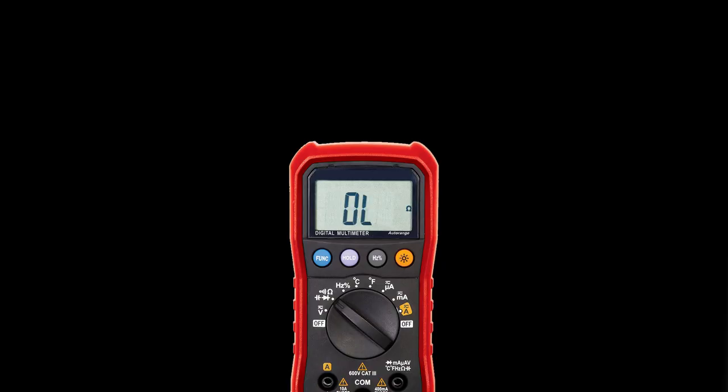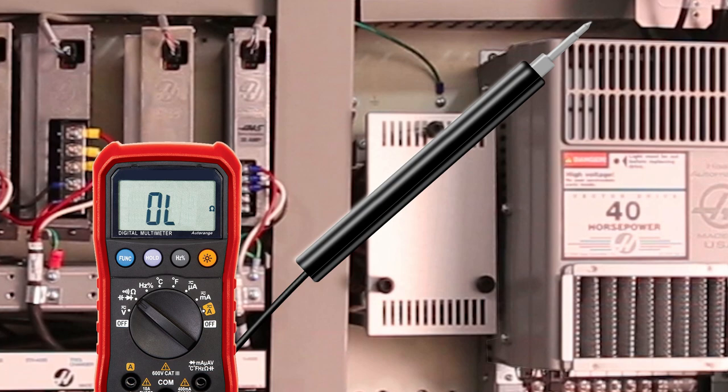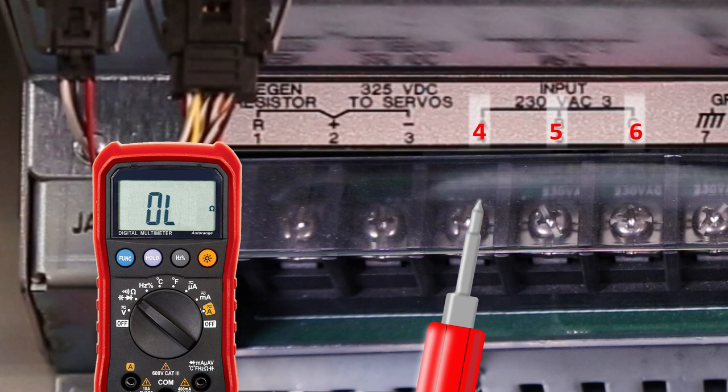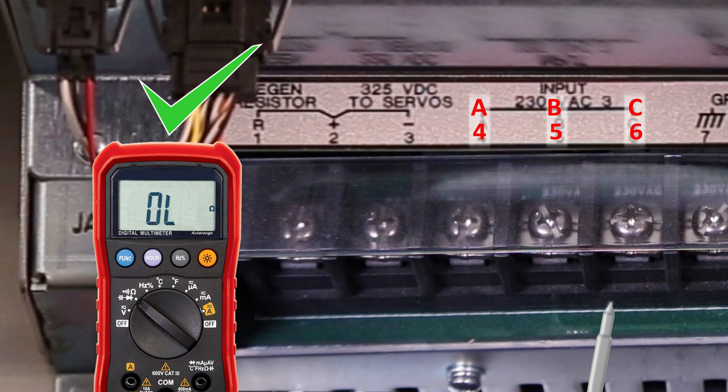Finally, check the status of the bridge rectifier. Still in resistance mode, touch the black lead to the machine chassis. Touch the red lead to terminals 4, 5, and 6. These are on the input side of the bus and are labeled A, B, and C.